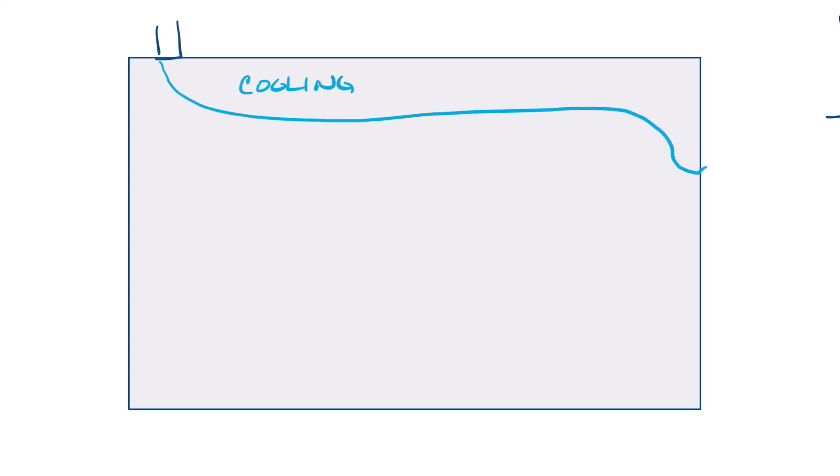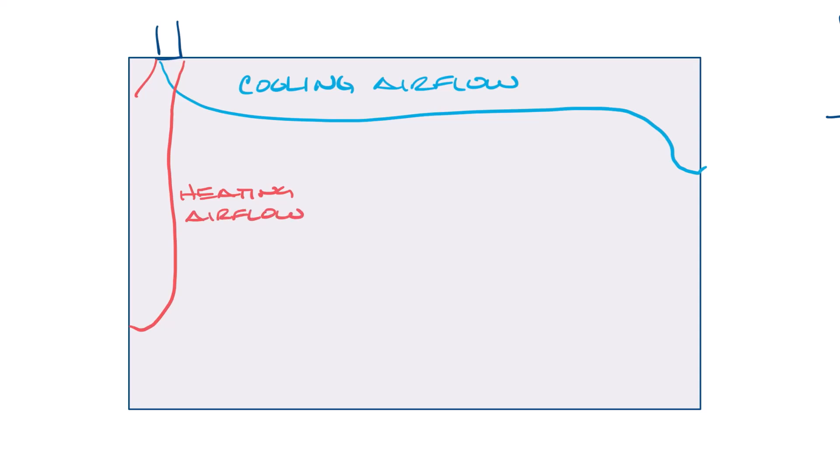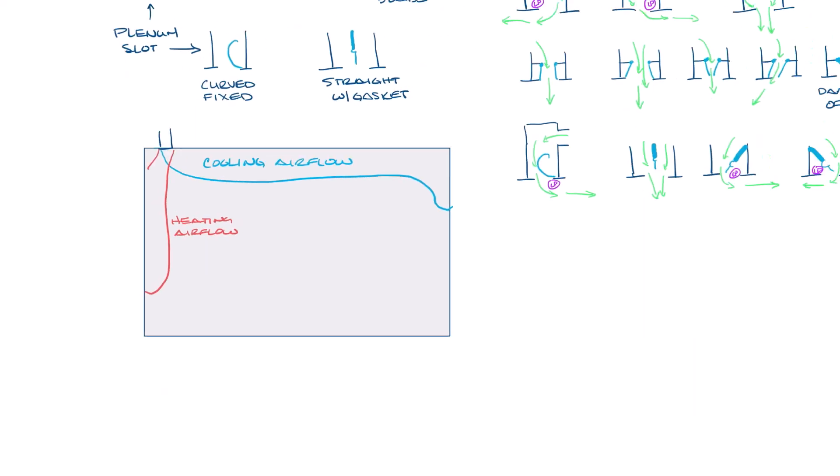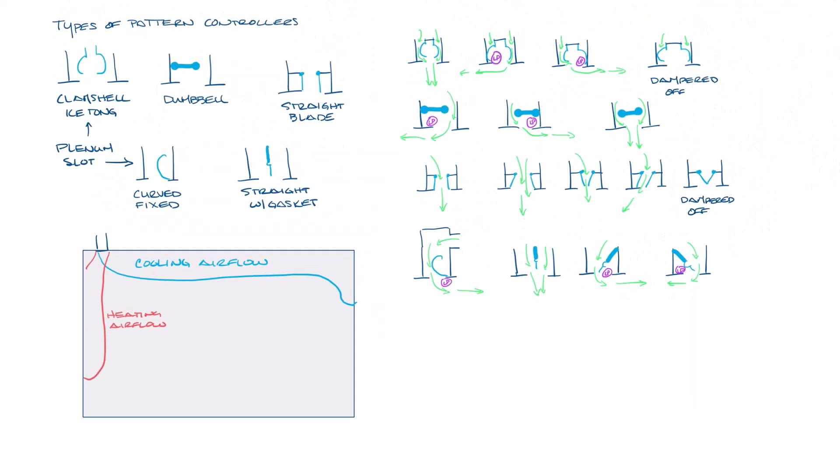So why do you want to adjust the pattern controllers? Well, in a typical installation, during cooling, you want the airflow to go across the ceiling and down the wall to roll the room. In heating, though, you would want the air to be in the direction of the perimeter wall or window so that you can get heat into the occupied space.